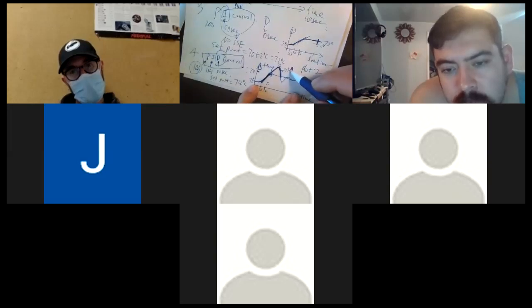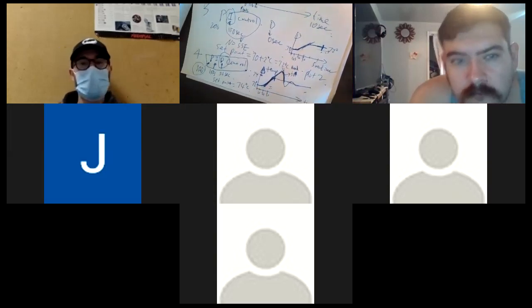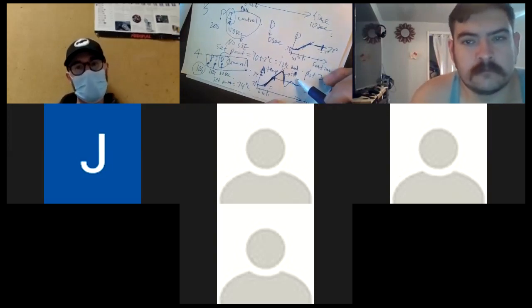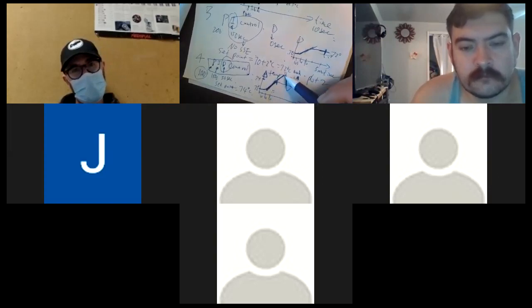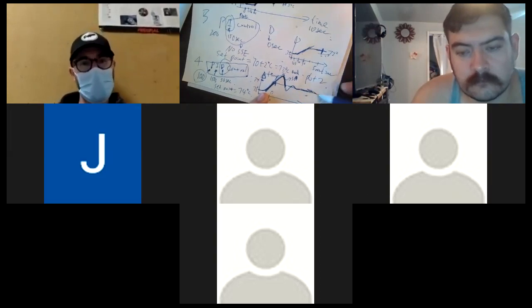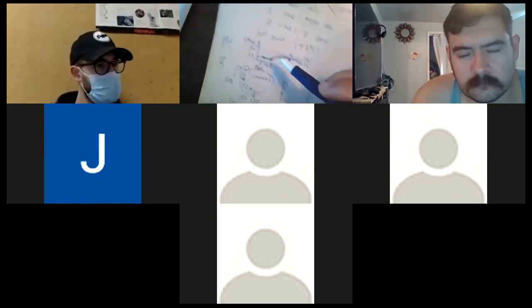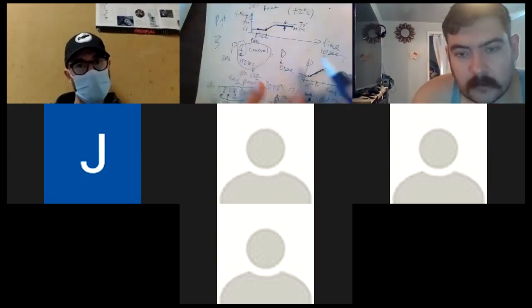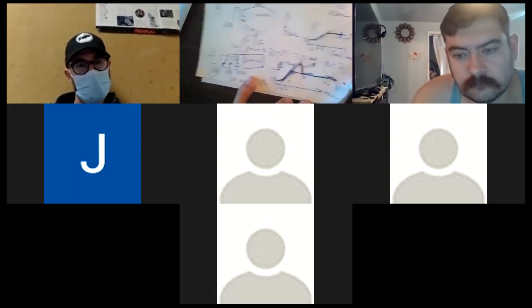In this case, I entered 50 as the band. I did it last night. It doesn't work very well. Obviously, we never want to put 50 as a proportional band, because it just goes right over. And then the temperature drop is very slow. It will take a long time to go back. After a couple of oscillations, it might end up at 74, but obviously that's not as good as this: just reach 74 and stabilize at 74.